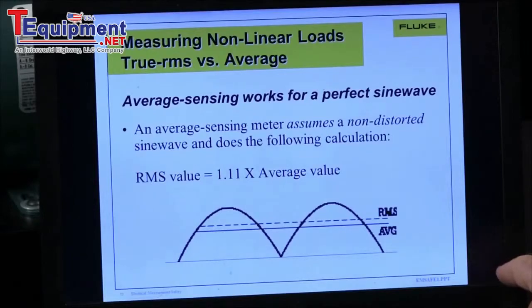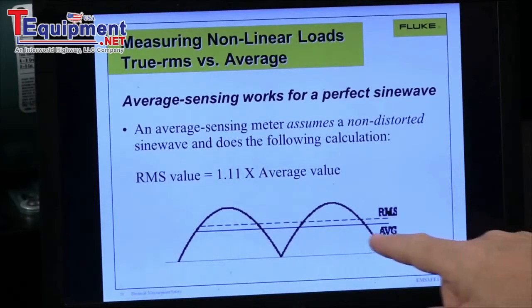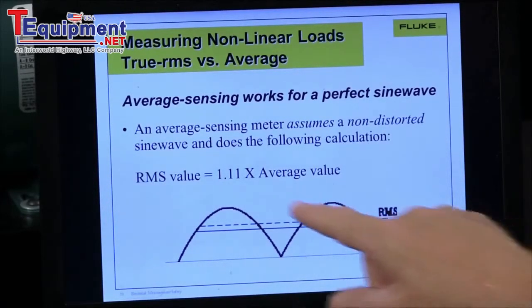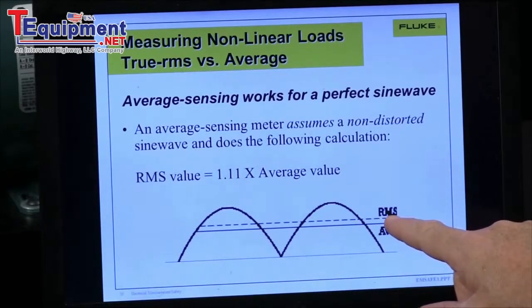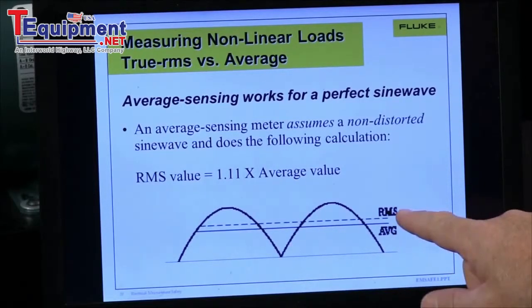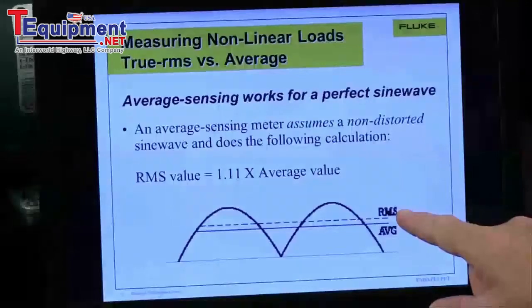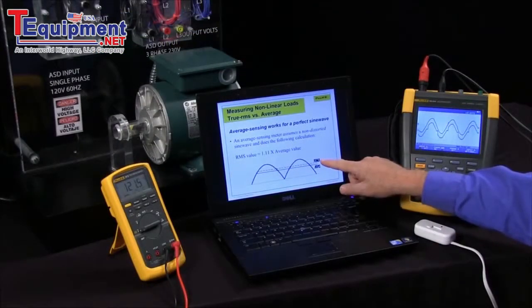If we use an average responding meter, what it does is it takes the average of a signal, multiplies it by 1.111, and then displays the RMS. So it's actually average sensing RMS display. This was fine when we had a world of nothing but linear loads.